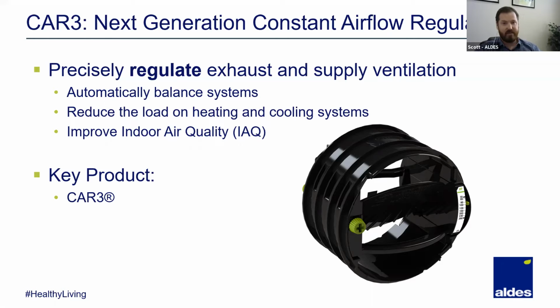So you can think of it as no different than any other balancing damper on the market, just with the difference being that it's going to maintain that airflow as your system parameters change, whether that's filters loading or stack effect, or operable windows and doors, or devices within an apartment turning on and off, like range hoods, dryers, things like that. These are going to compensate for those changes in static pressure within the system to maintain airflow all year long. And what that's going to do for your system is that it's going to reduce the load on my heating and cooling.